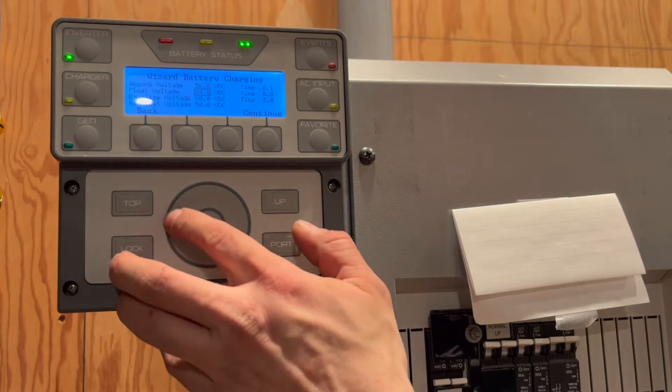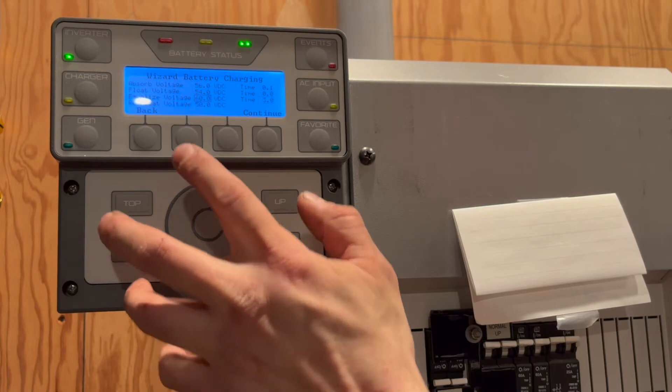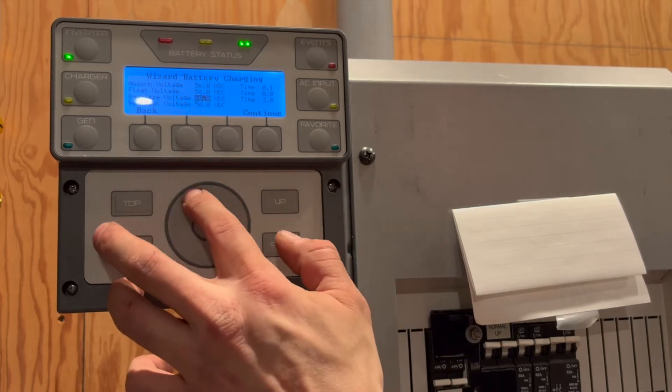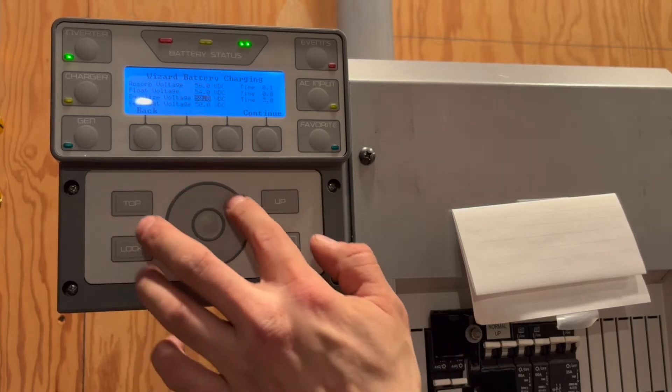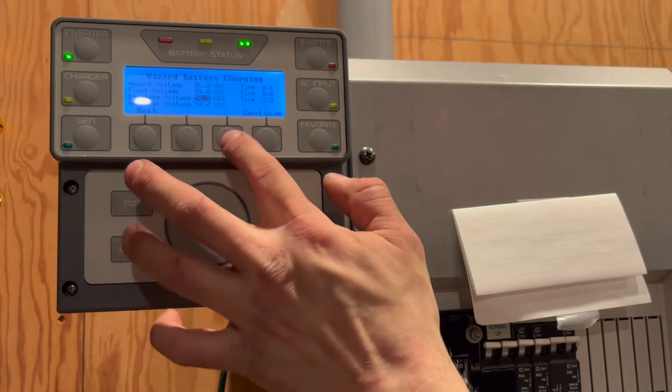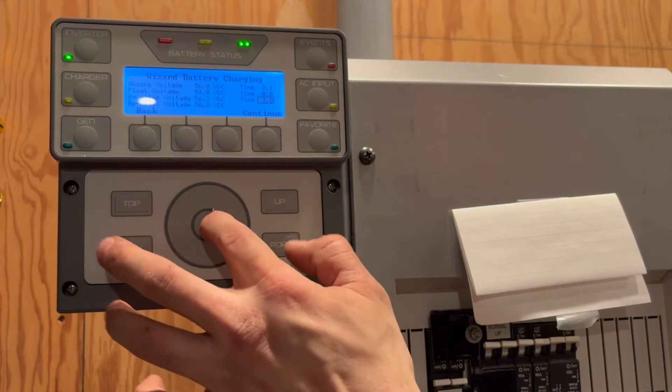Float would be set to 52.8 volts, but we are going to disable it by setting float time to 0 hours. Equalize will also be disabled, but it is still best to set the equalize voltage to about the same as the absorb voltage in case it is accidentally initiated.